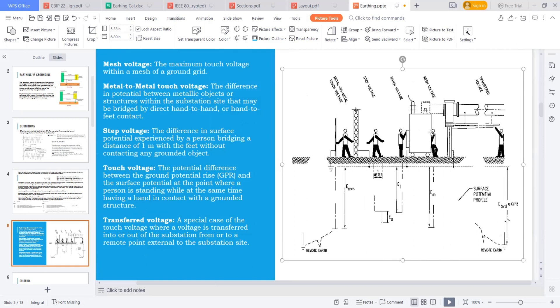And the person is leaning towards this, so it seems to be a maximum touch voltage. The maximum touch voltage is called as a mesh voltage. One more voltage is generally there — that is a transferred voltage. It is a special case of touch voltage where a voltage is transferred into or out of the substation from or to a remote point external to the substation. In the entire guide, we are mostly concentrating on these three things: step voltage, touch voltage, and mesh voltage.